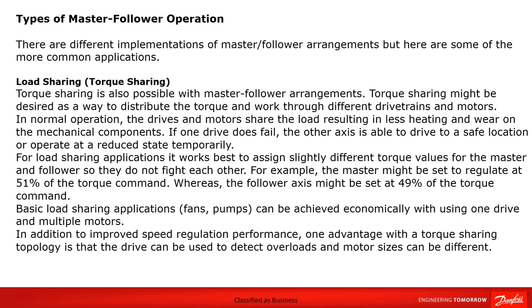Basic load sharing applications, like fans and pumps, can be achieved economically using one drive and multiple motors. And in addition to improved speed regulation performance, one advantage with a torque sharing methodology is that the drive can be used to detect overloads, and also your motor sizes can be different. They don't have to be the same size.